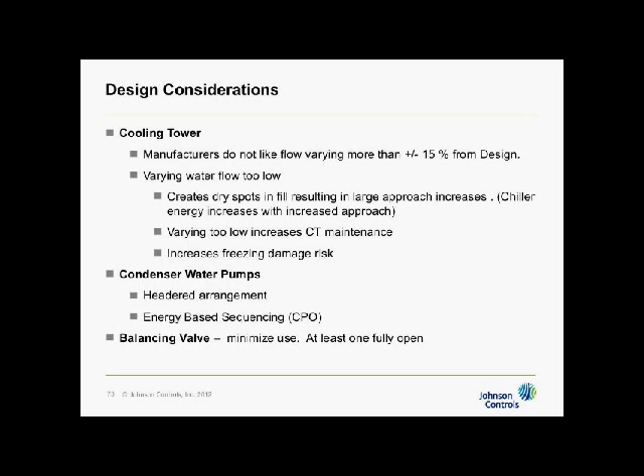On your condenser water pumps, again, as on the chill water, a headered arrangement enables you to optimize their usage. And of course, more importantly than all these, is using energy-based sequencing, or a CPO, to take advantage of the capabilities of the plant. You still need a balancing valve on your condenser water systems and chillers. You still want to minimize their use. One of them, when you balance everything, should be fully open.